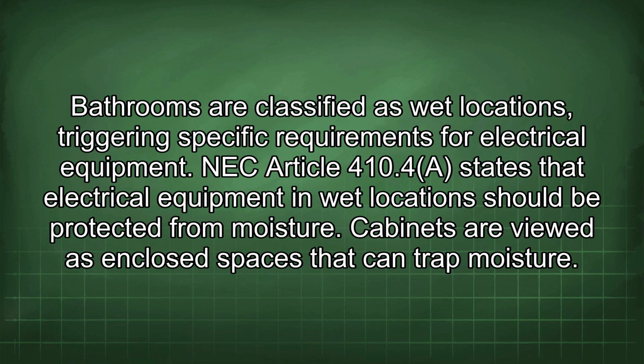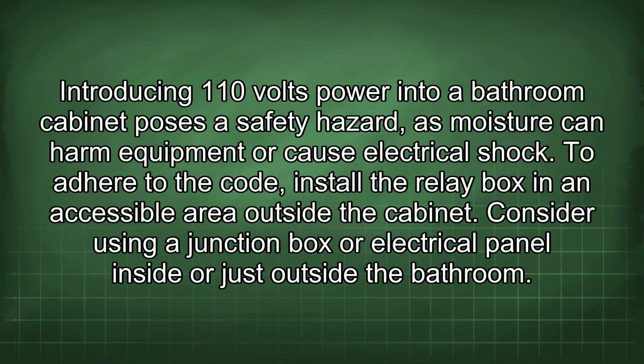Bathrooms are classified as wet locations, triggering specific requirements for electrical equipment. NEC Article 410.4 states that electrical equipment in wet locations should be protected from moisture. Cabinets are viewed as enclosed spaces that can trap moisture. Introducing 110 volts power into a bathroom cabinet poses a safety hazard, as moisture can harm equipment or cause electrical shock. To adhere to the code, install the relay box in an accessible area outside the cabinet.